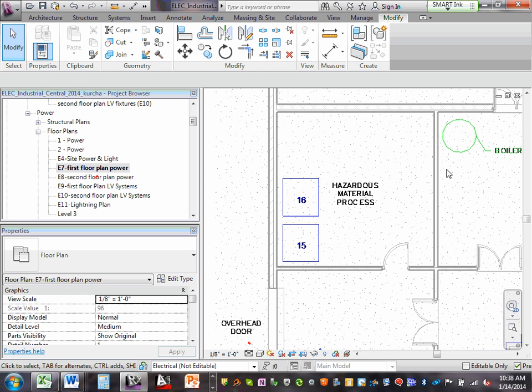The device itself, that explosion-proof smoke detector, as you call it, has nothing to do with its ability to withstand the explosion. I apologize for the confusion. What it means is that it is constructed in such a way that there is no potential for electrical arc inside that device. The atmosphere in this room is explosive in nature. Therefore, the room is rated as an ANSI Class 1 Division 1 atmosphere.